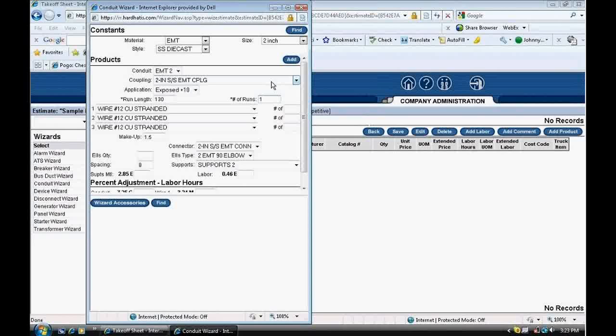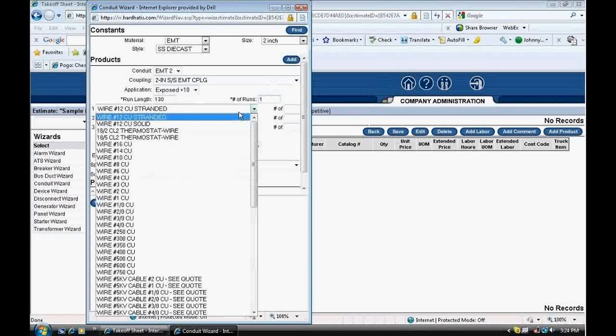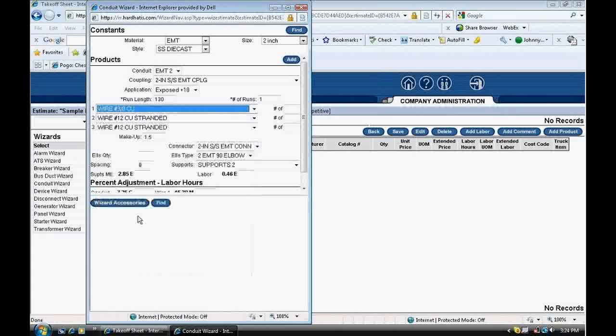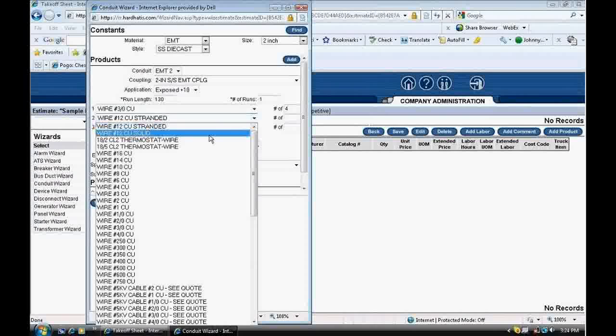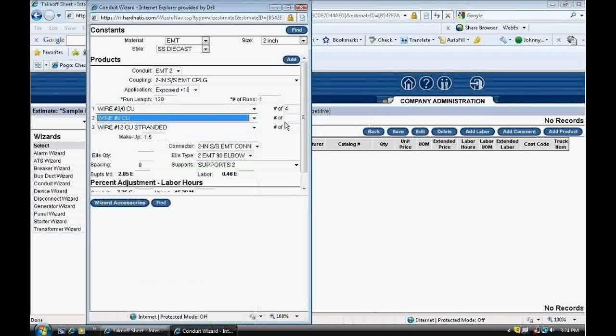Next, I enter the four 3-aught copper wires in one number 6. I click the wire drop-down, select 3-aught copper. In the number of box, I type in the number 4 for four 3-aughts. Next, I'm going to do the ground wire. I click the drop-down, find my number 6 wire, number of, quantity of 1.